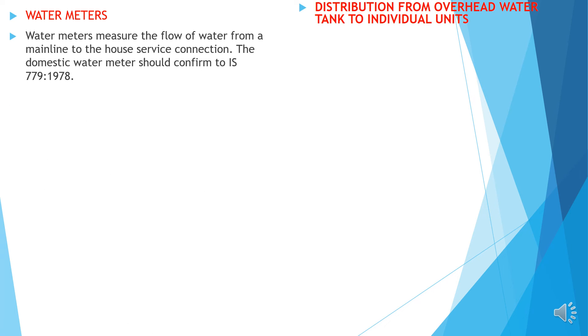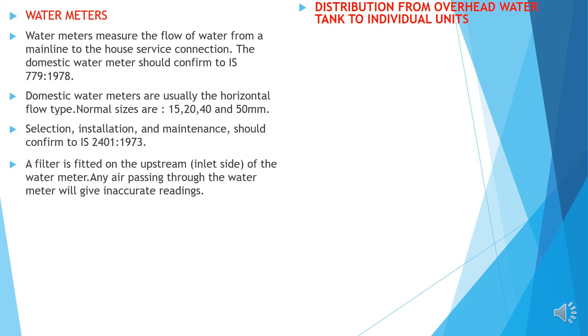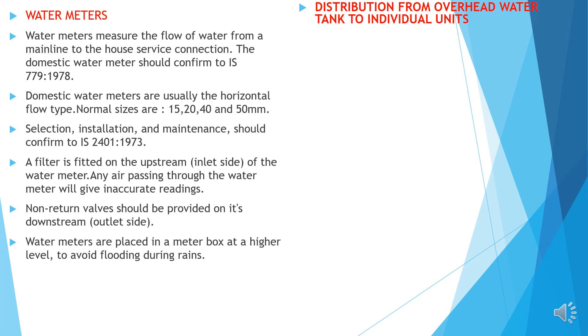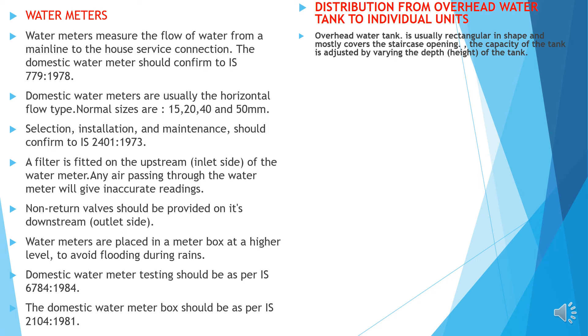Water meters: the water meter measures the flow of water from a main line to the house service connection. The water meter should confirm to IS-779. Domestic water meters are usually the horizontal type; normal sizes range from 15 to 50 mm. Selection, installation and maintenance should conform to IS-2401. A filter is fitted on the upstream (inlet side) of the water meter. Any air passing through the water meter will give inaccurate readings. A non-return valve should be provided on the downstream (outlet side). Water meters are placed in a meter box at a higher level to avoid flooding during rains. Testing should be as per IS-6784 and the domestic water meter box should be as per IS-2104.